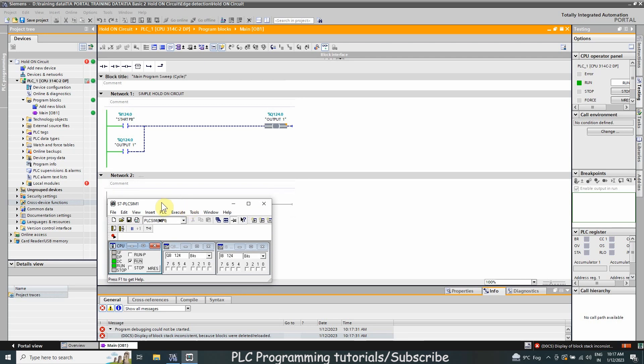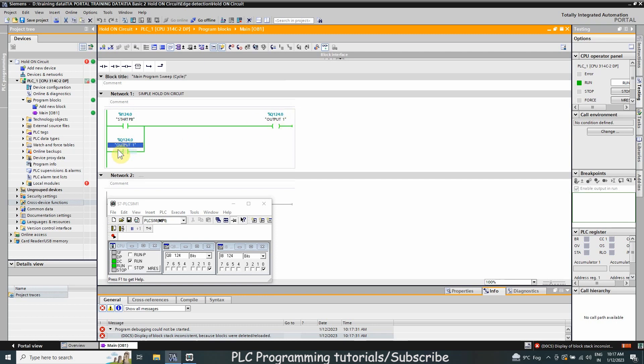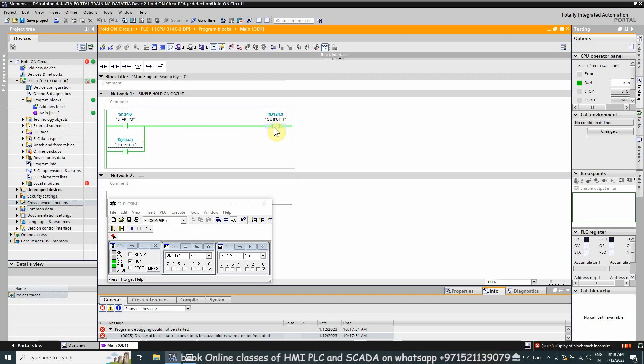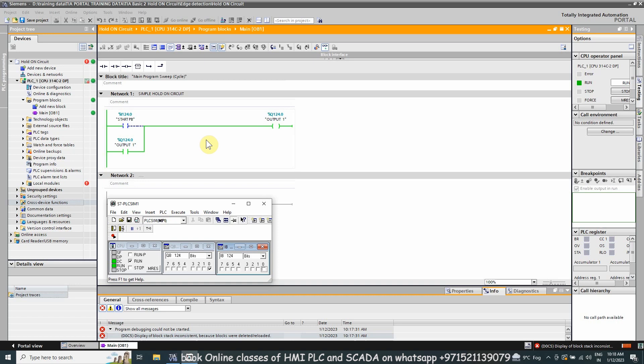Now, as I turn on I124.0, it turns on output coil Q124.0, and its contact is also closed because we assigned the same address to this normal open contact. From here the output Q124.0 is latched on, and if we release push button I124.0 the output still remains on. However, we cannot turn off Q124.0 now — to turn it off we need to use a NC contact here.